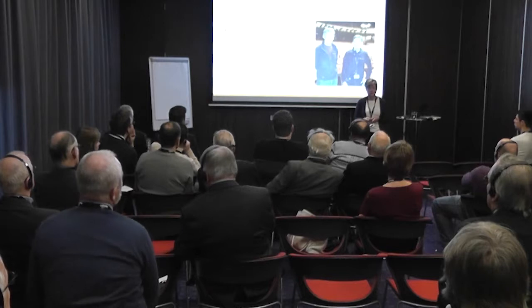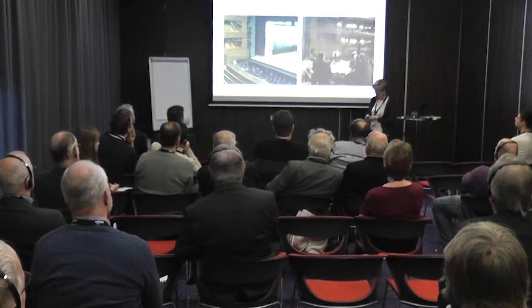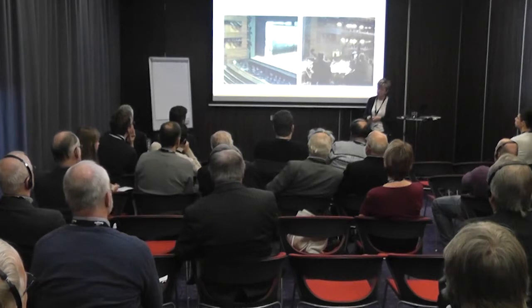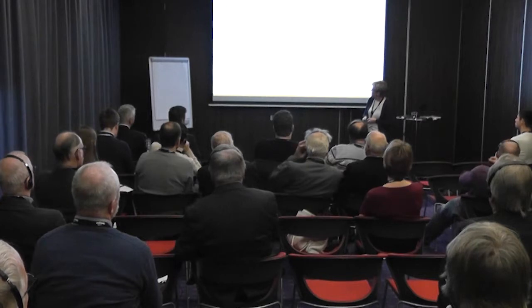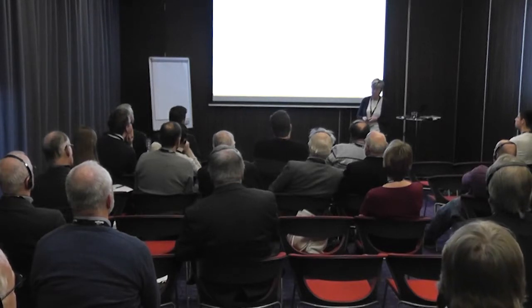Yes, as I said, there are challenges with the orchestra pit, and there have been studies working on this, with measurements and putting smoke and measurements of humidity and temperatures. So we have been trying to find out, and here we can see from one test period that the temperature is quite stable, but the humidity fluctuates between below 30 and up to 40%. While in the main theater, it's quite a stable situation.